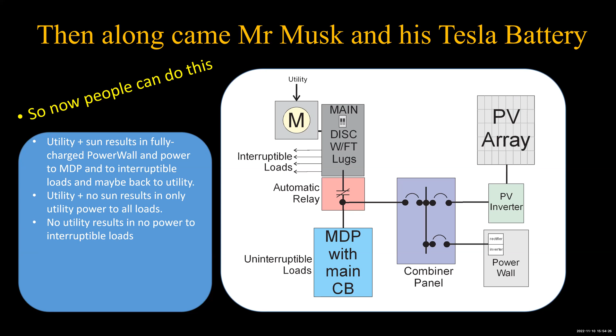The only thing is, you've got to be careful: if it's nighttime and your batteries are running low, you've got no way to charge them since the utility is gone, and there has to be some control in there to make sure that when the sun comes up the next morning, that storage system can tell the PV array it's okay to turn on, because it has use for the electricity, since the utility isn't there to give the message to the PV that it's okay to turn on.